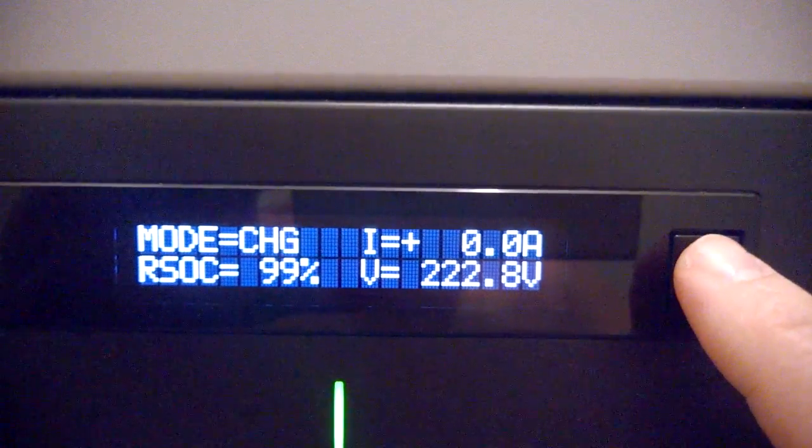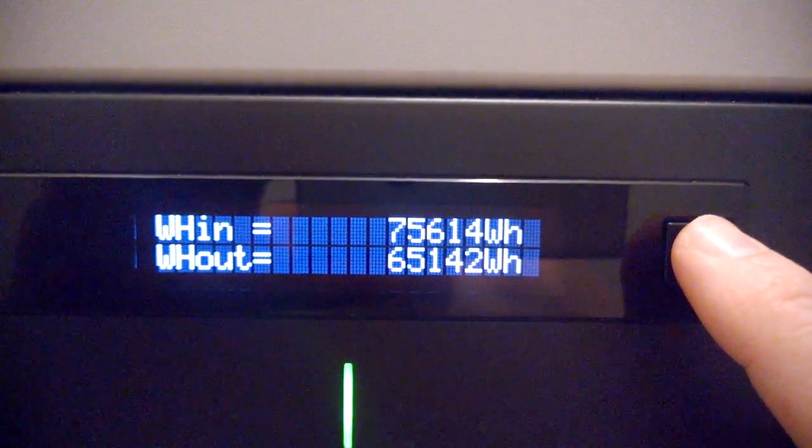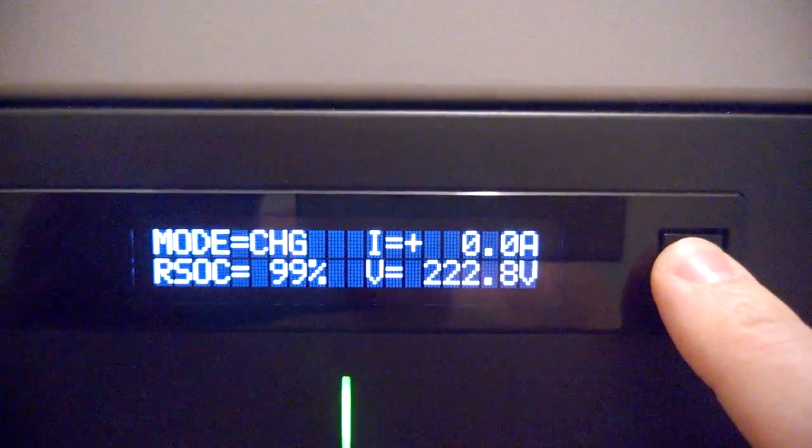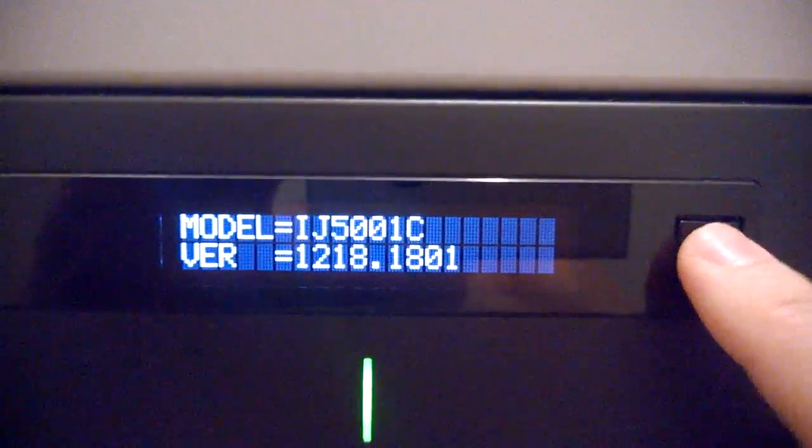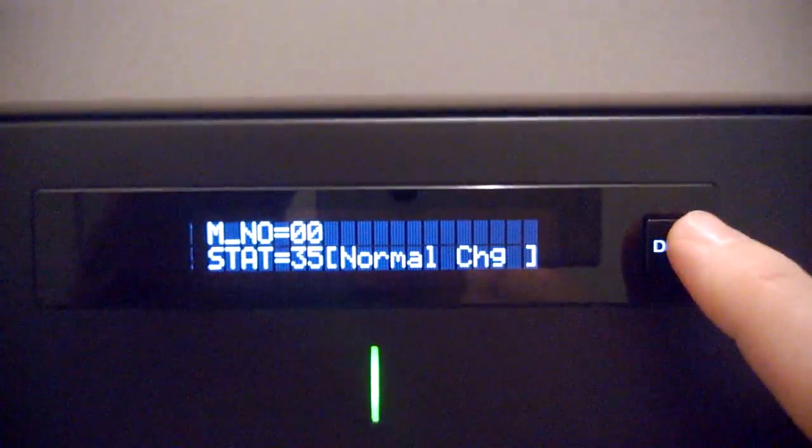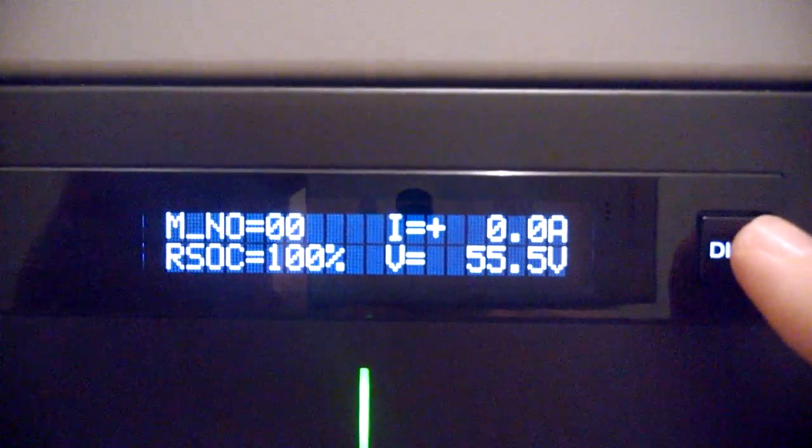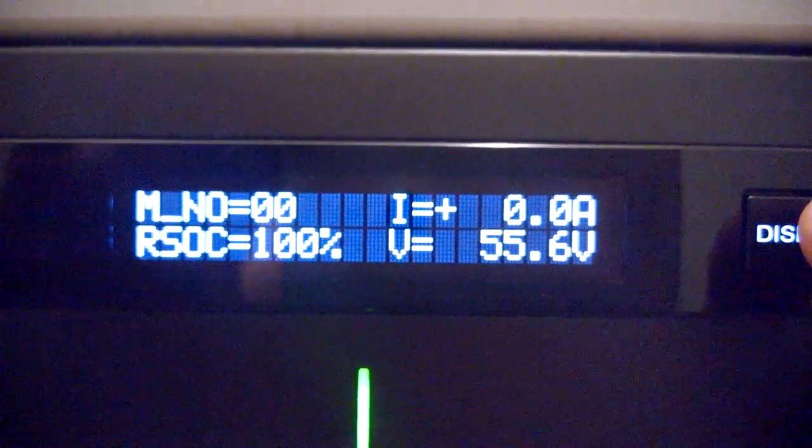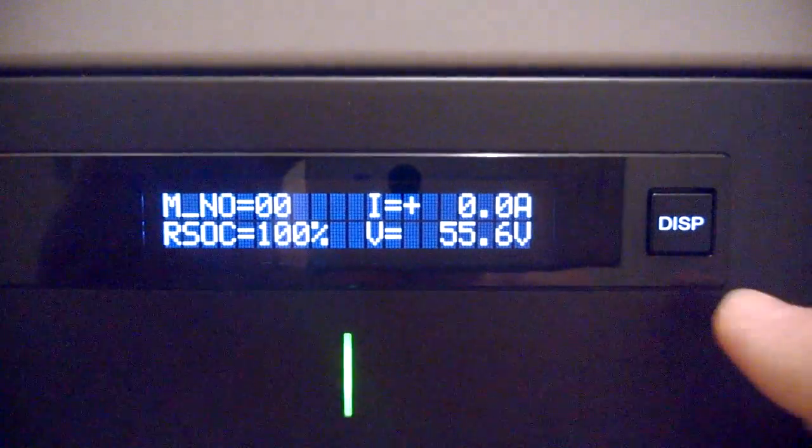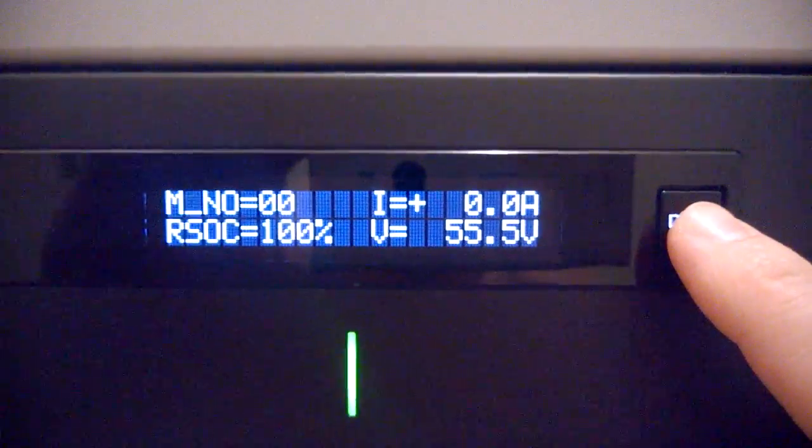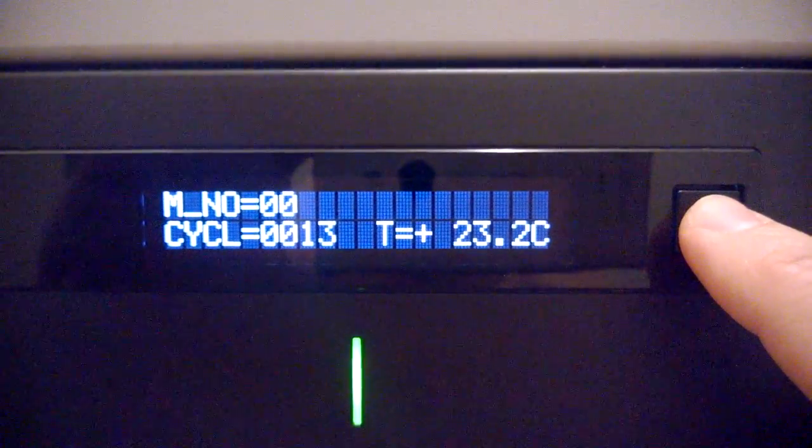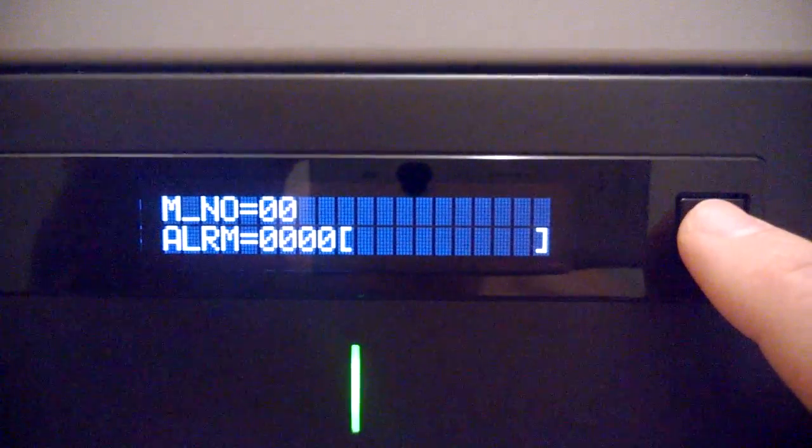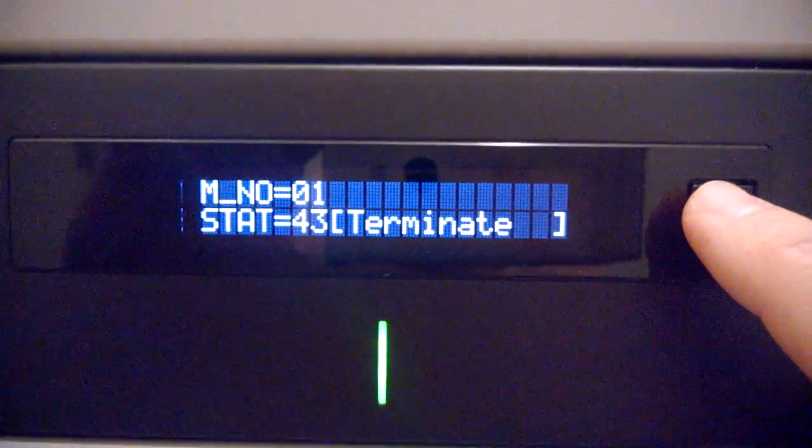So this is how I can check each module. This is the first one, and it's still charging though it says 100% rated state of charge, 55.5 or 56 volts, no alarm during cycles.